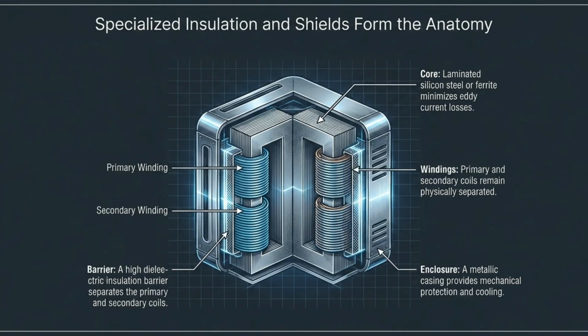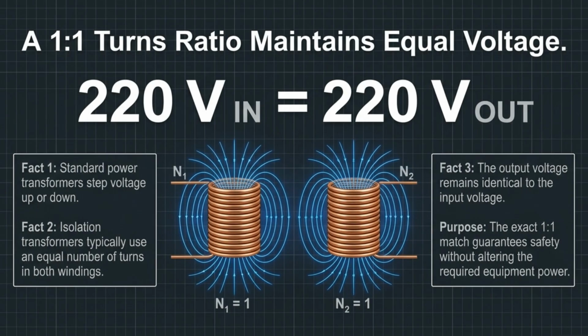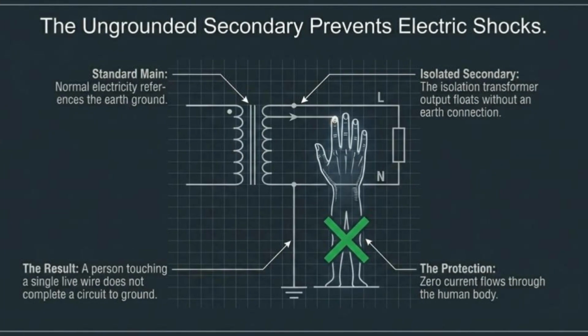dielectric barrier for insulation. Isolation transformers typically use a 1-to-1 turns ratio, which maintains equal voltage between the input and output. This exact match guarantees safety without changing the required equipment power, unlike standard transformers that step voltage up or down. The ungrounded secondary coil is a vital safety feature. Since the output floats without an earth connection, touching a single live wire does not complete a circuit to the ground. This means zero current flows through the human body, preventing electric shocks.